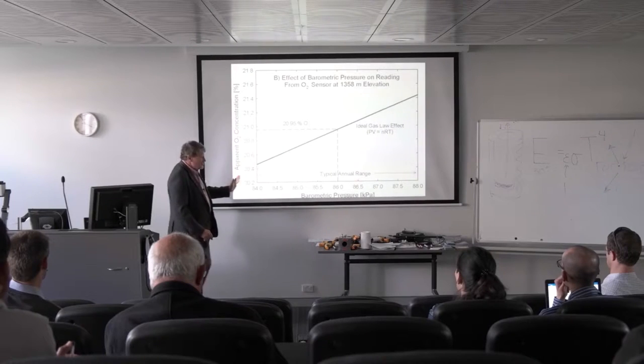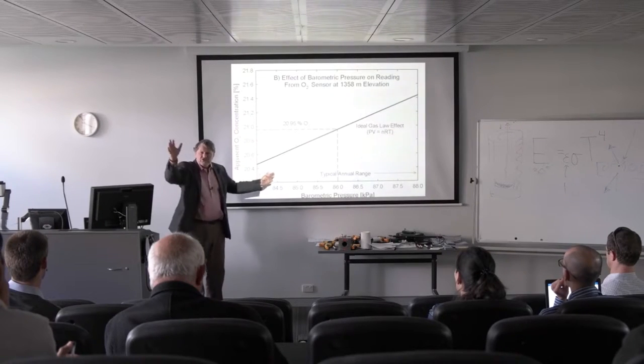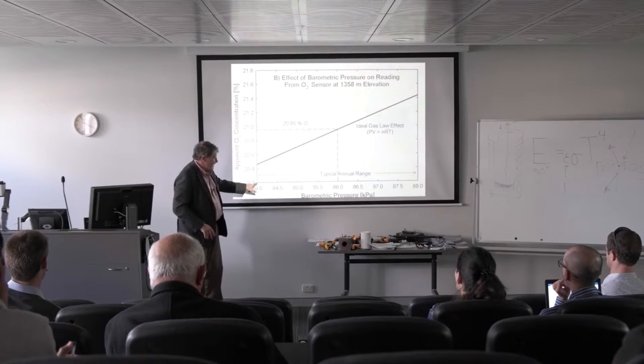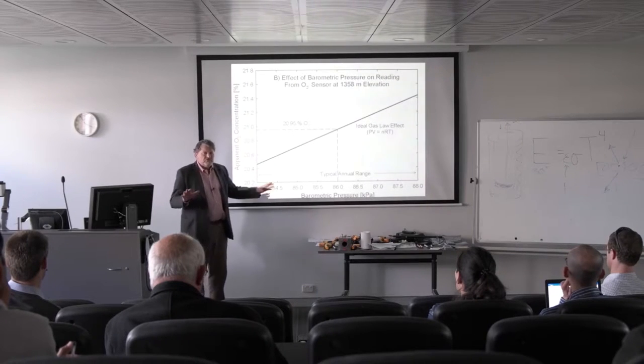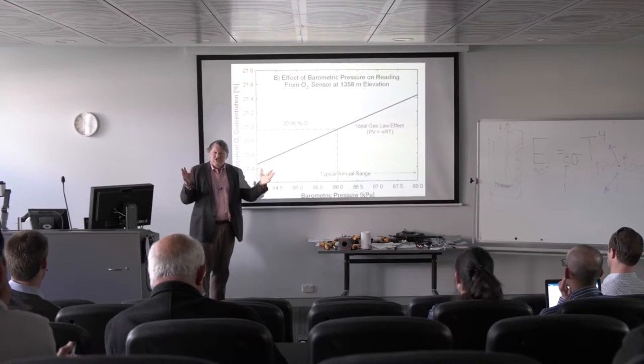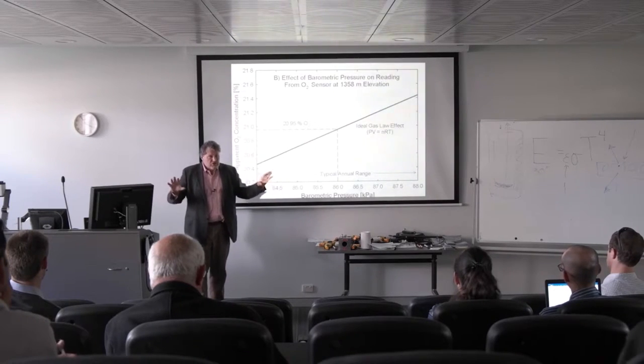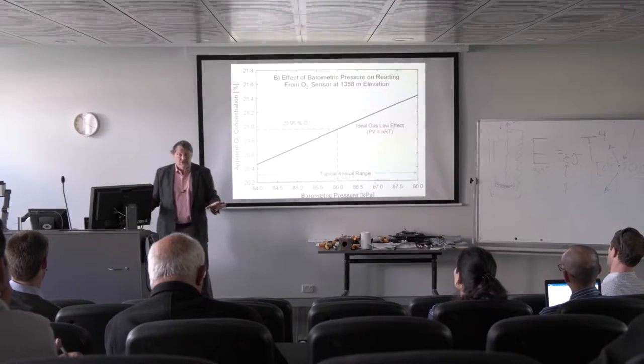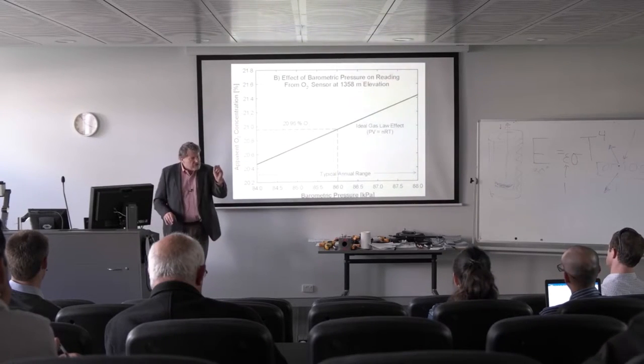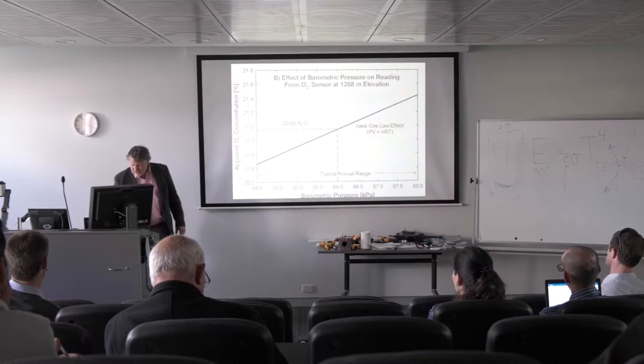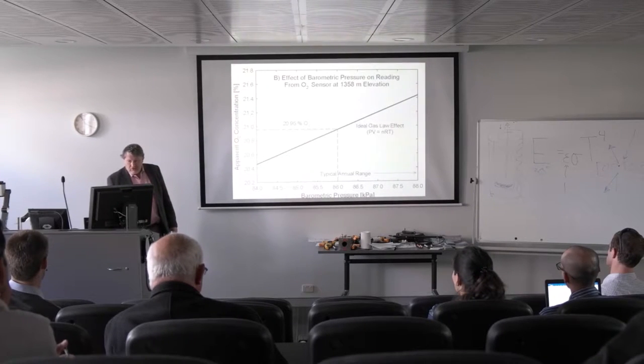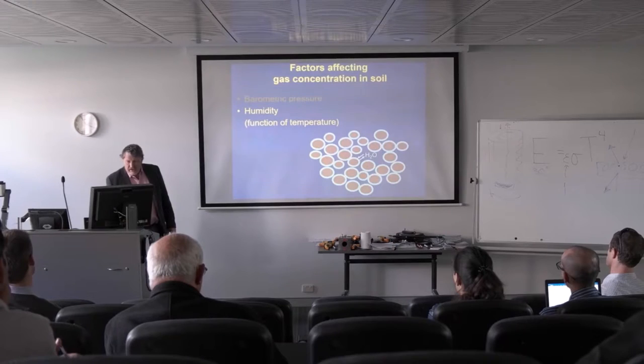Pressure doesn't change that much — high pressure fronts, low pressure fronts. Pressure from highs to lows only changes the density of air about one percent, maybe two percent in extreme events. So even though pressure has a huge effect on our weather, it only has a small effect on the density of gas. But we measure and correct for it.